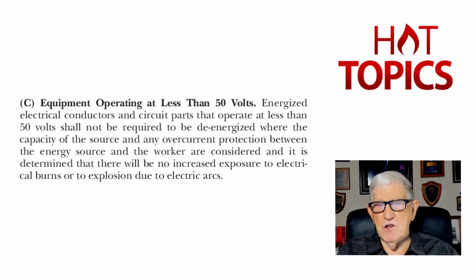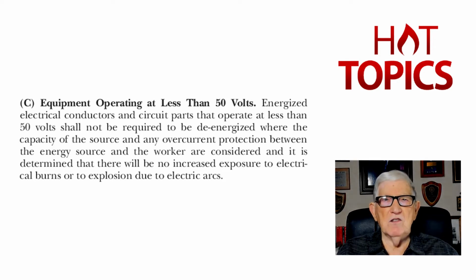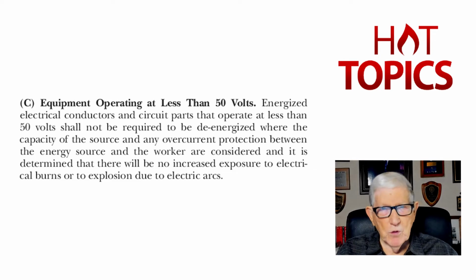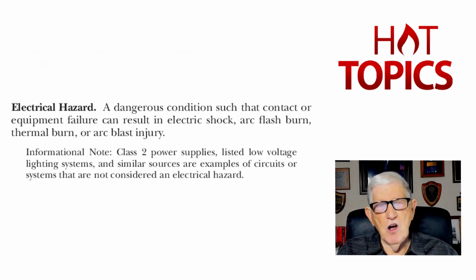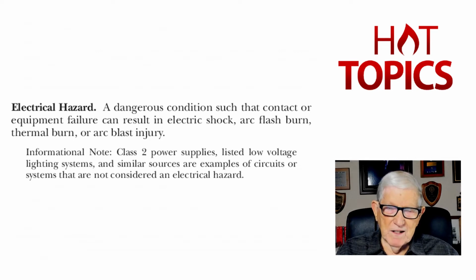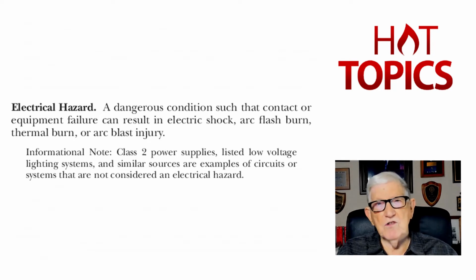Now, he was concerned. He said, I thought you could work on Class 1, 2, or 3 circuits without any problem at all. But now, again, 70E gives some information that's important to us. So we want to look at Article 100 of 70E, and we want to read the definition. Remember this, electrical hazard. And it basically says that only a Class 2 power source listed with low voltage for lighting systems and similar type equipment such as computers and things like that are examples of circuits that 70E and OSHA do not consider a problem.